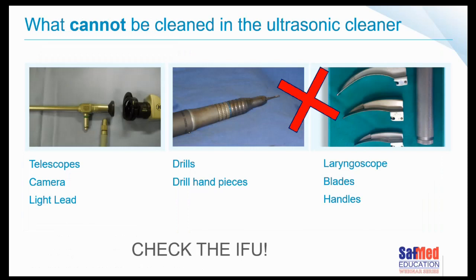We spoke last week in depth about instructions for use, looking at the manual before cleaning any devices you buy. Things that cannot be cleaned in an ultrasonic cleaner include drills, handpieces, telescopes, cameras, light leads, and laryngoscope blades and handles. Those devices will be injured in some way if put in an ultrasonic cleaner, even if they are submersible. You'll shake all the bits loose, and that becomes problematic.